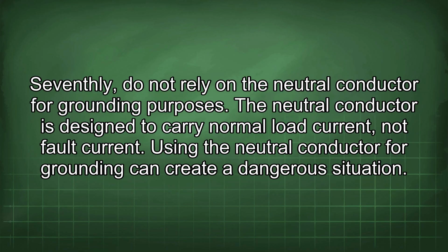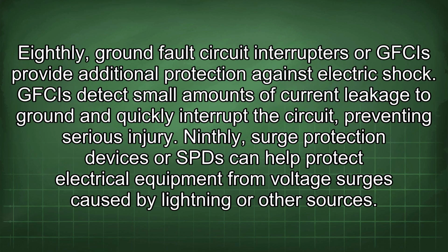Seventhly, do not rely on the neutral conductor for grounding purposes. The neutral conductor is designed to carry normal load current, not fault current. Using the neutral conductor for grounding can create a dangerous situation. Eighthly, ground fault circuit interrupters or GFCIs provide additional protection against electric shock. GFCIs detect small amounts of current leakage to ground and quickly interrupt the circuit, preventing serious injury.